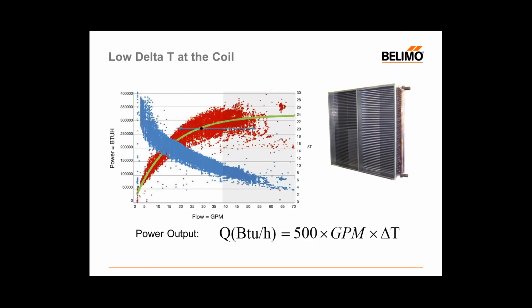And we really want to look at, I don't ever want to use anything off to the right there. And in this case, maybe we don't ever need to go past, we got 37, 38 gallons a minute to produce the load that's in place here. And so this is what we're talking about. It's not just a full flow, full load problem, because a lot of places don't run at high load demands all the time, but you can still generate low delta T's even at partial load, especially in the shoulder seasons where our production of cooling is much higher than the load demand in the space, and we wind up with low delta T's then. Can be really tricky to diagnose in a central plant type environment.